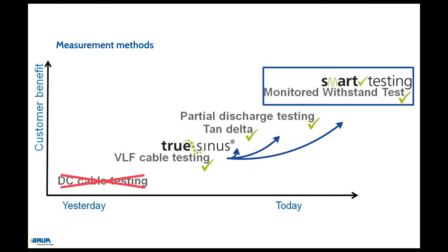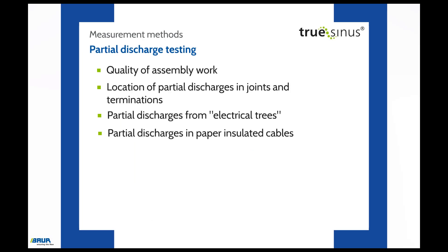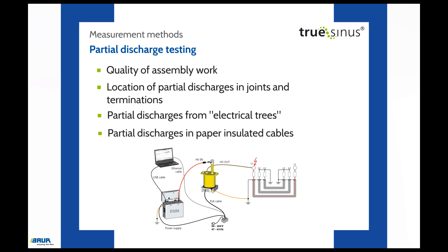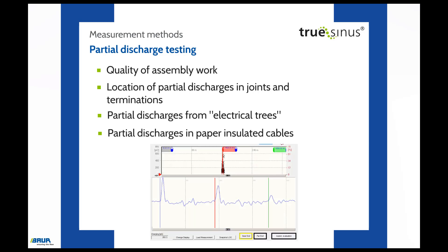The partial discharge testing provides information about the quality of fitting work and locates partial discharges in joints, cable terminations, electrical trees in XLPE cables, and PDs in paper-insulated cables. The following equipment is required: a VLF voltage source, an appropriate coupling capacitor, and a PC to control the complete process. With this combination of measuring devices, the information can be found and the measurement results supplied.